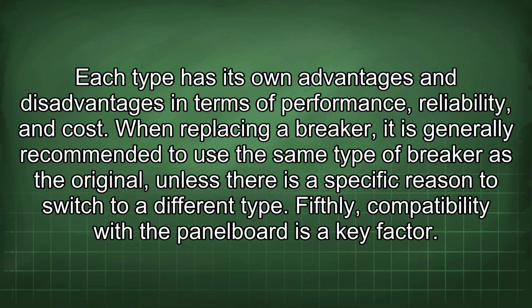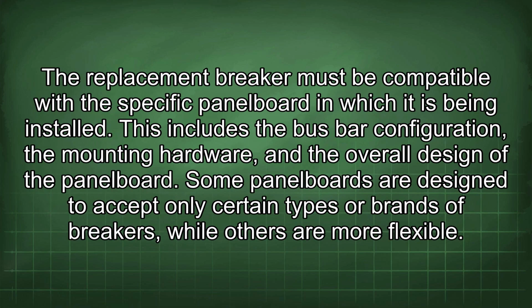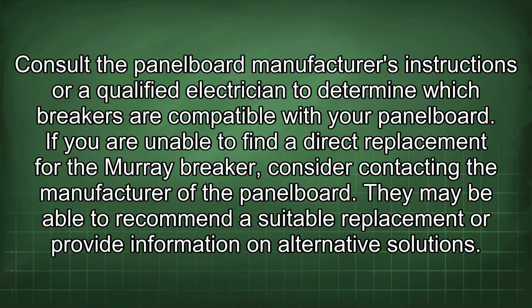Fifthly, compatibility with the panel board is a key factor. The replacement breaker must be compatible with the specific panel board in which it is being installed. This includes the busbar configuration, the mounting hardware, and the overall design of the panel board. Some panel boards are designed to accept only certain types or brands of breakers, while others are more flexible. Consult the panel board manufacturer's instructions or a qualified electrician to determine which breakers are compatible with your panel board.